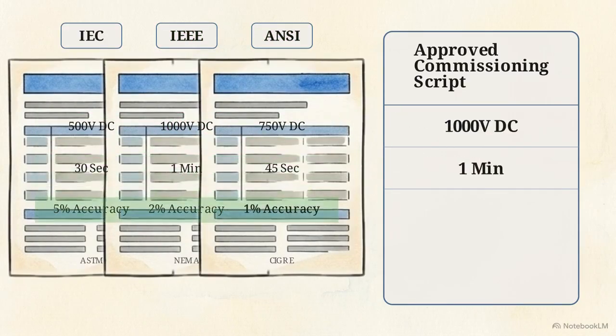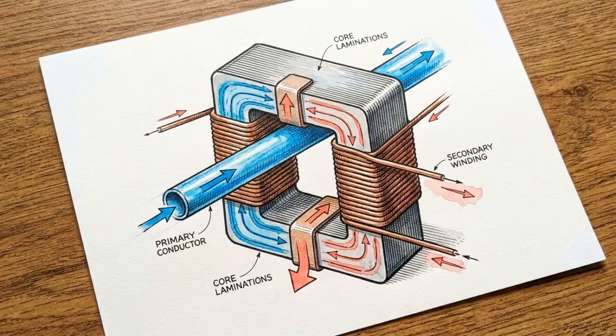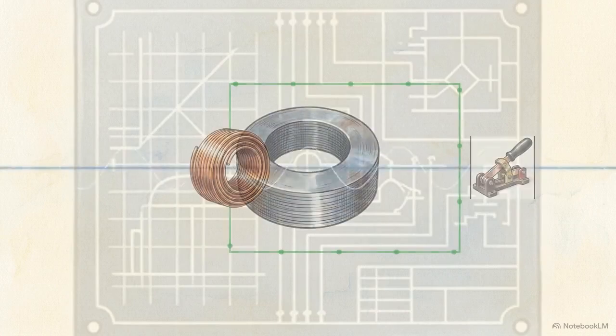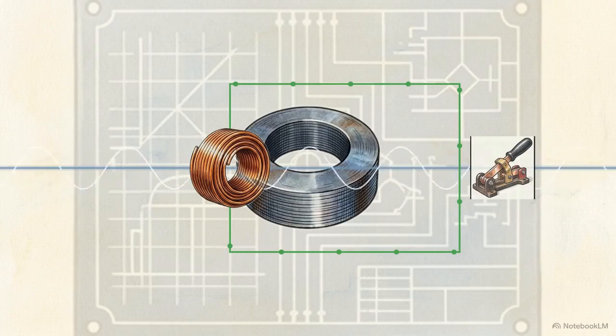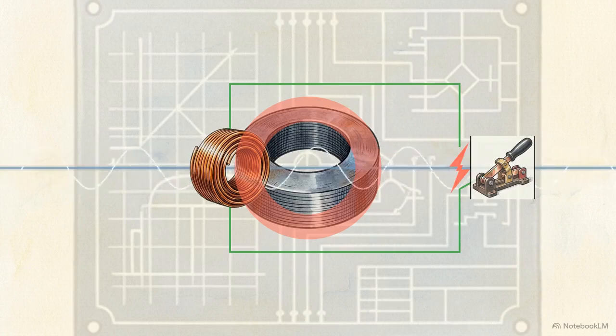To resolve conflicts between codes, specialists adhere to a single governing rule: always apply the most stringent approved requirement. The procedures we follow are dictated by a specific physical hazard. A CT is essentially a step-up voltage transformer operating in reverse. If you open the secondary circuit while the primary is under load, the opposing secondary ampere turns drop to zero. The magnetic flux inside the core immediately surges, inducing a theoretically infinite voltage across those open terminals.